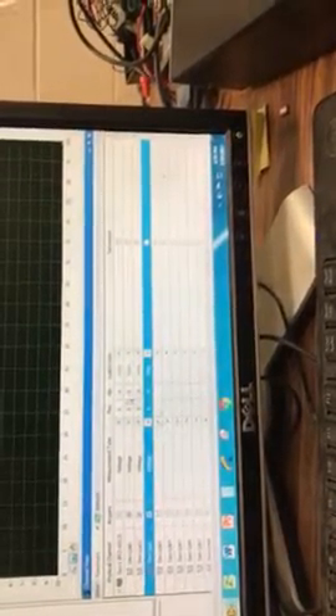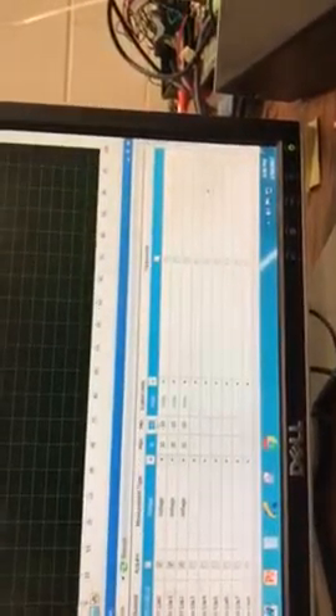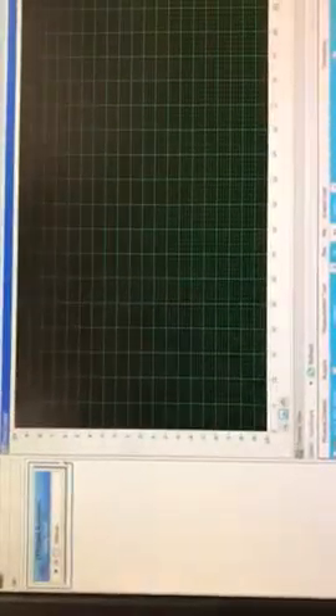In the meantime, I'm setting up Signal Express. This is the front view screen of Signal Express, and here I'm going to specify the channels. A0 is the transducer near the valve, as you can see, A1 is the angular sensor, and A2 is the upstream transducer. Here I'm going to define the voltage range. It's positive 10 to minus 10 volts. This is the default setup. I was working with a 1K rate and 100 samples to read. As you can see, it's continuous, differential, all of them the same.